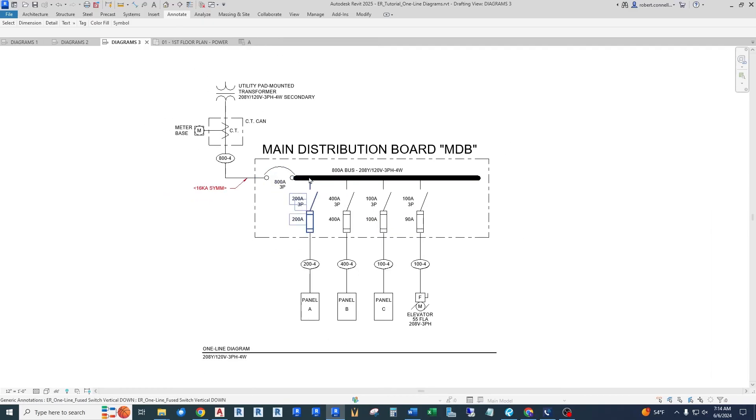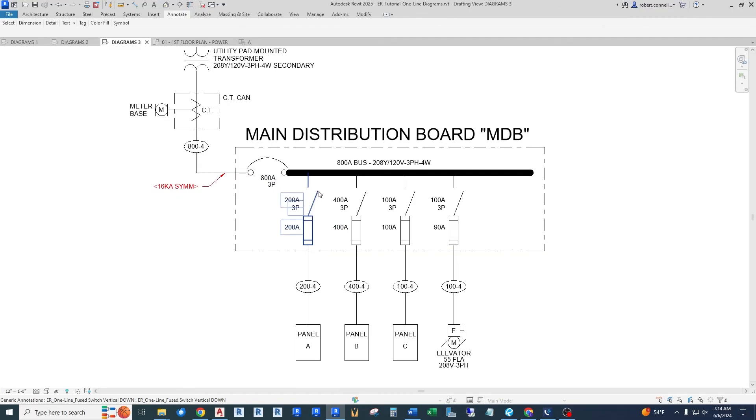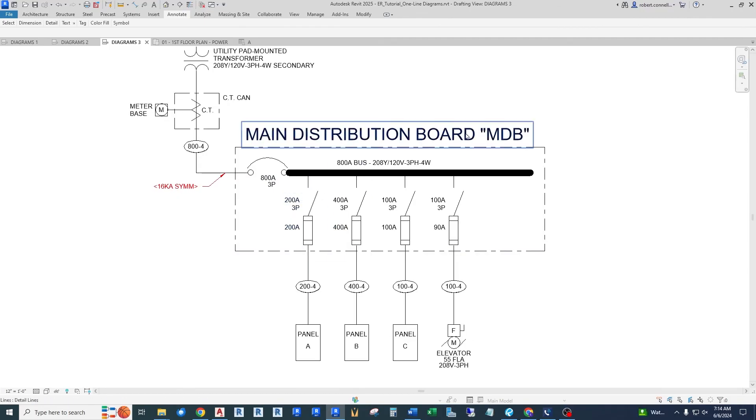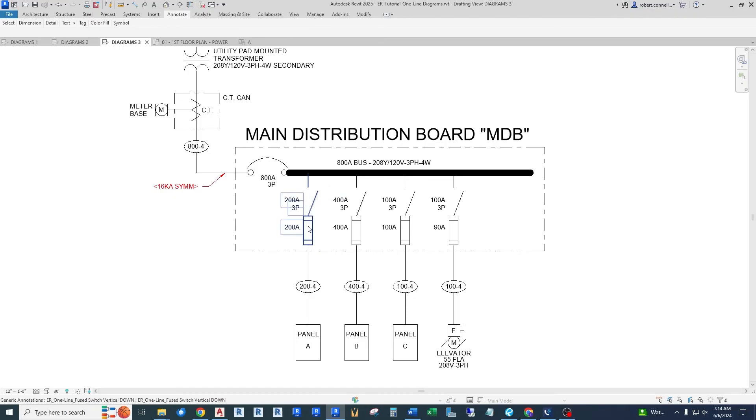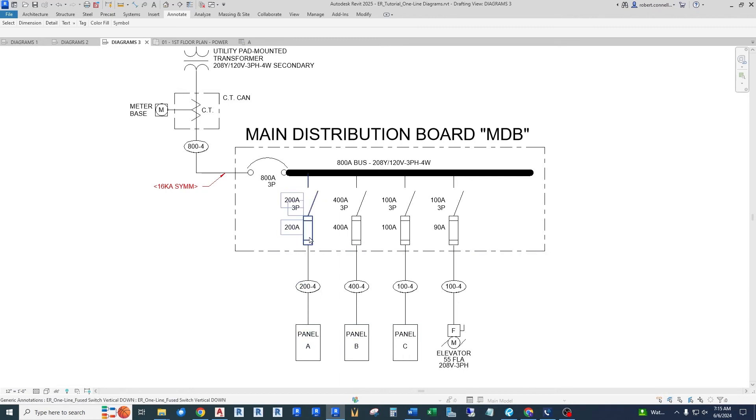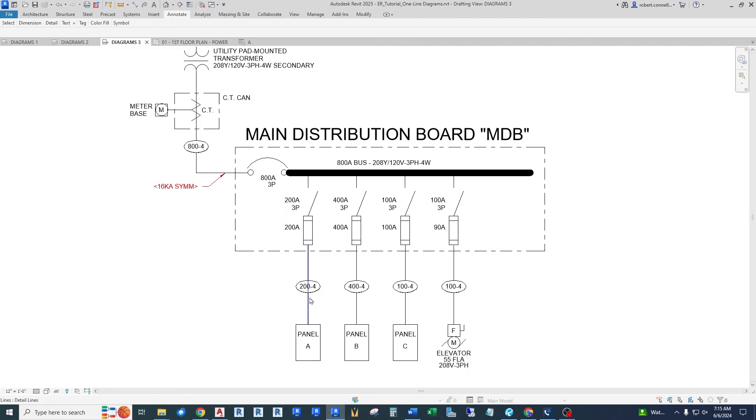And then this comes into the main distribution board, which is a large panel that in this case has a main circuit breaker protecting this entire bus. And then tapping off that bus are actually, these are symbols for switches and fuses instead of circuit breakers. This board, in this case more of a switchboard than a panel, has four fuse switches. And these feed different panels, panel A, B, and C, and they're different sizes. You can see different fuse sizes, different feeder wiring sizes. This single line represents multiple wires inside a conduit or cable.